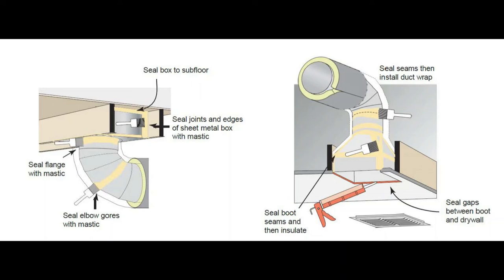While metal ducts are inherently smoother than flex duct, elbows in either type of duct work matter. One elbow in a duct is equivalent to over 30 feet of straight duct. In some cases, one elbow can be equivalent to 90 feet of straight duct. Transitions should be smooth and gradual, allowing for direct airflow with little turbulence. Poor duct installations lead to pressure imbalances and poor indoor air quality, the opposite of what ventilation systems are intending to achieve. Taking the time to properly design and install ductwork eliminates common callbacks and comfort complaints down the road.